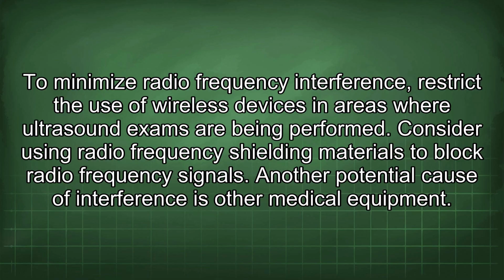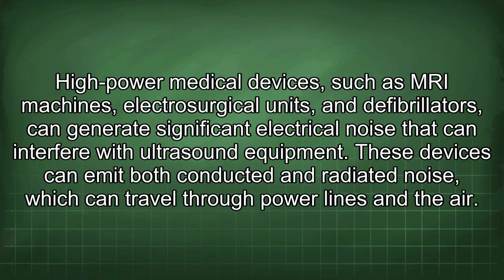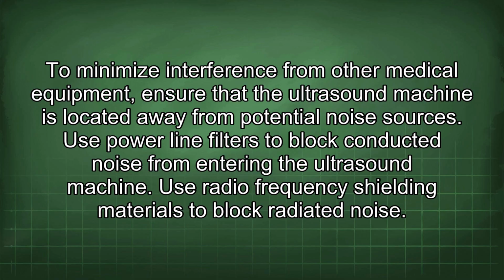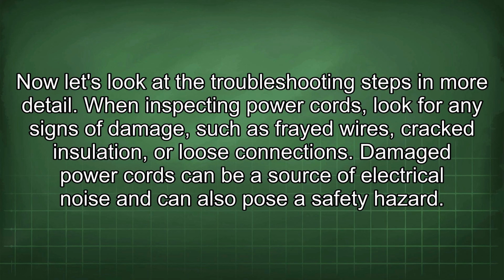Another potential cause of interference is other medical equipment. High-power medical devices, such as MRI machines, electrosurgical units, and defibrillators, can generate significant electrical noise that can interfere with ultrasound equipment. These devices can emit both conducted and radiated noise, which can travel through power lines and the air. To minimize interference from other medical equipment, ensure that the ultrasound machine is located away from potential noise sources. Use power line filters to block conducted noise from entering the ultrasound machine. Use radio frequency shielding materials to block radiated noise. Now let's look at the troubleshooting steps in more detail.